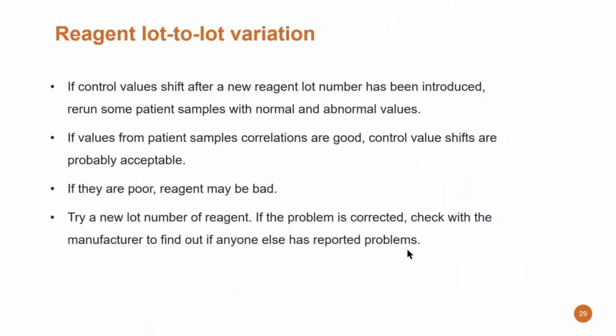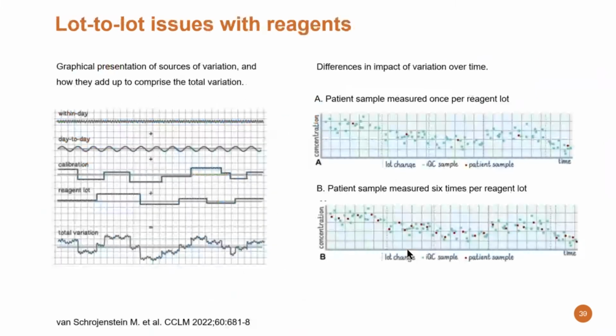Talking now about the reagent lot-to-lot variation. If control values shift after a new reagent lot number has been introduced, then rerun some patient samples with normal and abnormal values. If those values from patient samples correlate well, the control value shift is probably acceptable. If they are poor, you have to consider that the reagent may be bad. Try a new lot number of the reagent. And to be fair to the manufacturer, if you have such a problem, which you corrected by using a different lot number, please inform the manufacturer that this happened so that they can inform others about this problem.